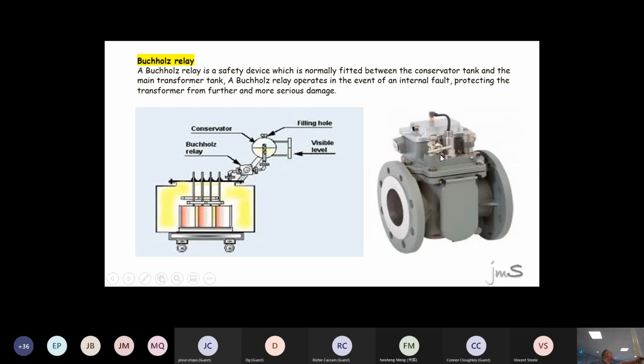When I was an apprentice, every Friday we had a transformer. We had to go and service these Buchholz relays. Once every 6 months we had to do one. And you can imagine if I do one every Friday, there's quite a bit of transformers we had to service. And also you find that there were switches where we switch it off, close it, for oil not to flow through. Once we close it, we drain it, and then we do it. But that transformer will be switched off because there's always standby transformers at hospitals or places like that. Anyway, that was good times in those days.